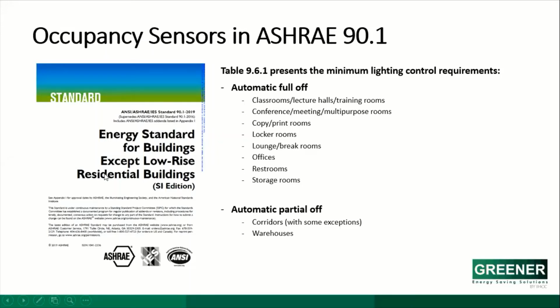Giving a quick background: when it comes to energy efficiency, LEED and other green building certifications mainly use standard 90.1 as a reference. Section 9 of the standard deals with lighting and lighting control requirements. Per table 9.6.1, which presents minimum lighting control requirements, occupancy sensors are required in automatic full-off mode for rooms like classrooms, conference rooms, locker rooms, offices, and restrooms, and in automatic partial-off mode in areas like corridors and warehouses—corridors with some exceptions mentioned in the standard, like certain healthcare corridors.